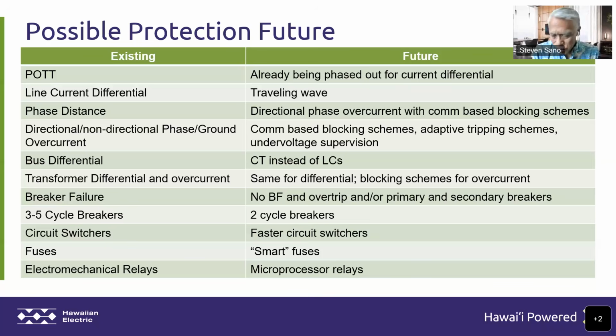Electromechanical relays, of course, continue changing those out with microprocessor relays. And sort of along that same vein, replacing microprocessor relays with the next generation. We still have some first generation microprocessor relays on our system back from the 90s. Okay, so that's sort of what the future for our protection systems look like. Changes that will have to be done to accommodate our decarbonization and change to inverter-based generation.